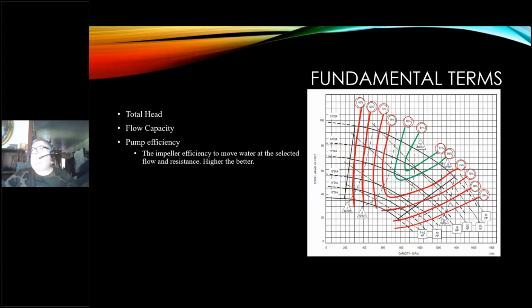Okay, efficiencies. Pump efficiency is going to change according to what impeller you've got. Now, I've outlined in this case the green lines. The red lines are where the efficiency is starting to fall off. So the best efficiency this pump can exhibit is in the 81% range, and that's only including, in this case, two impeller curves. If you can accept 80% efficiency, you get down into a third curve. However, if you start dropping off at 75, you can get into a fourth curve, but it's way down the line. And if that's acceptable, fine. But this is basically the pump's impeller ability to move that water.